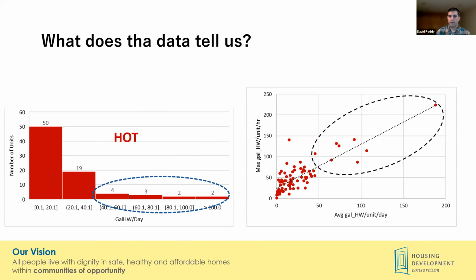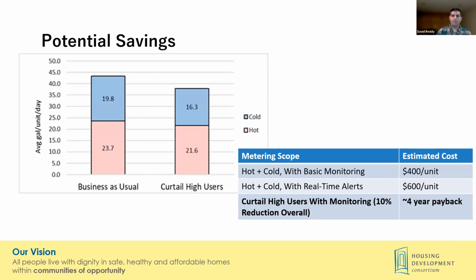This is just another way of looking at it: how much hot water per unit per day at the max those units were using. This is really important because we talked about the design load, how much hot water the water heating system and pipes need to support delivering at a given time. These outliers can really influence or affect that assumption, so if we can wrangle them, there's a lot of opportunity for savings.